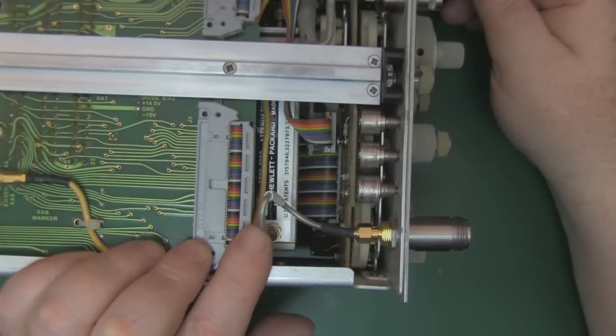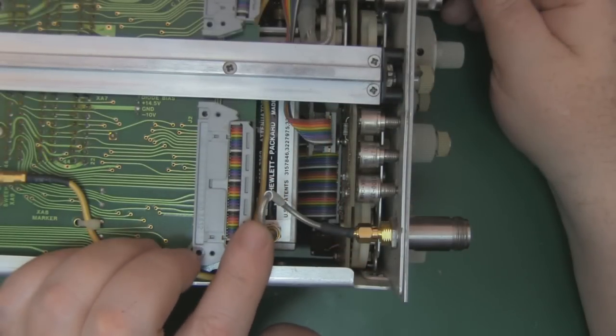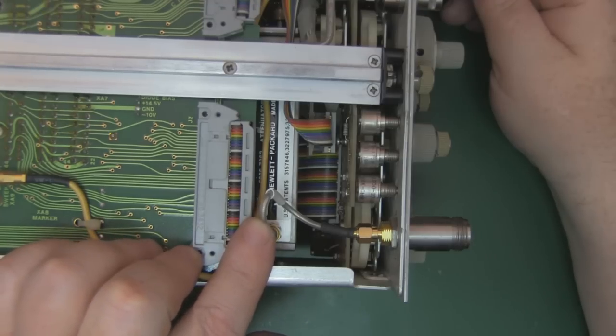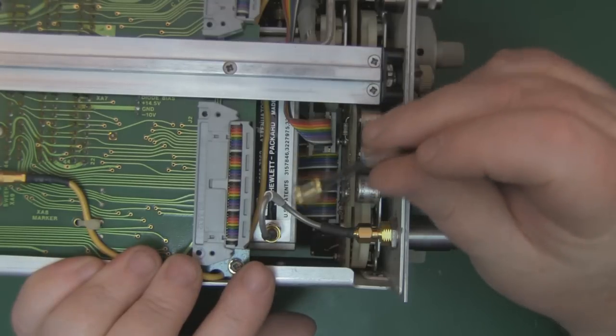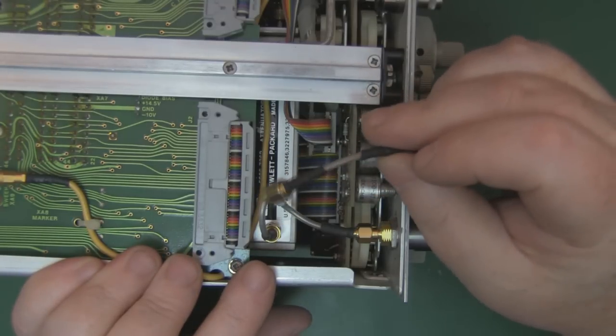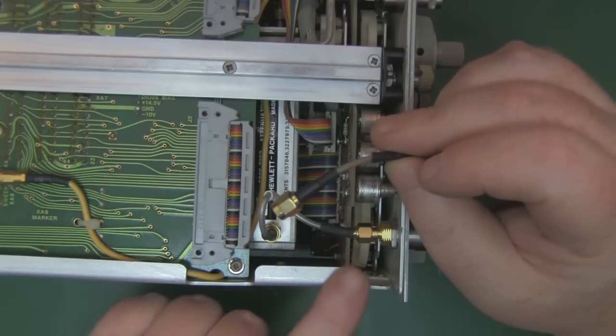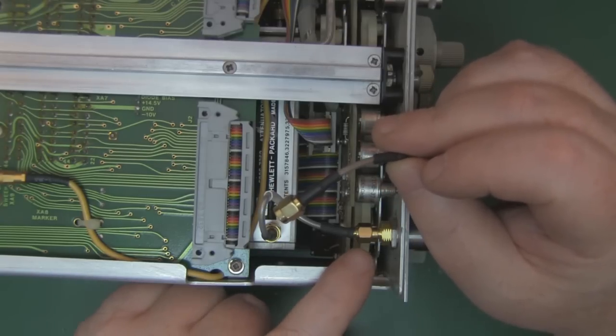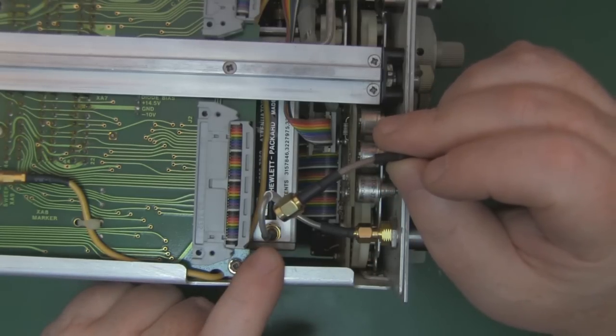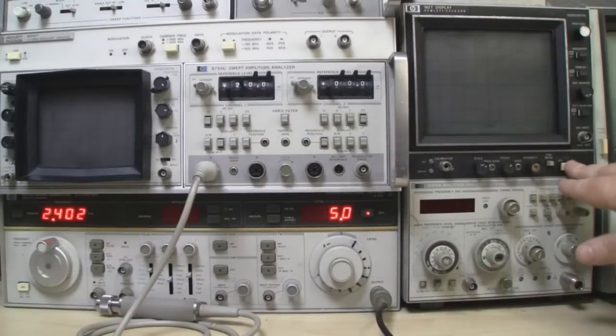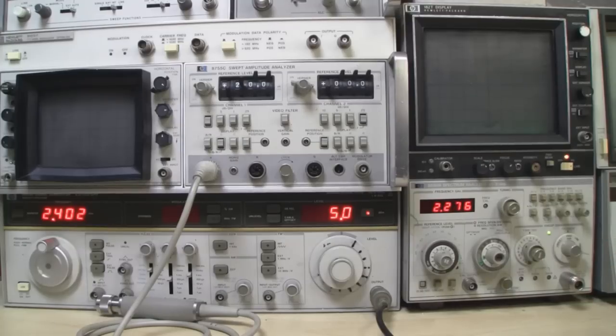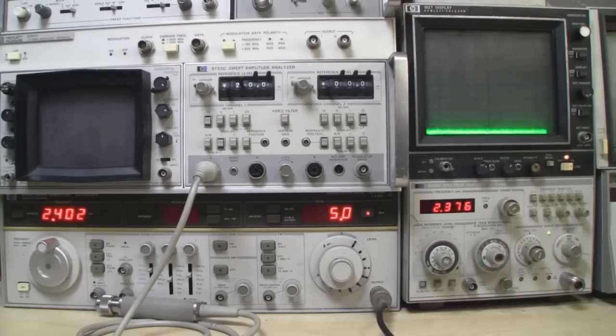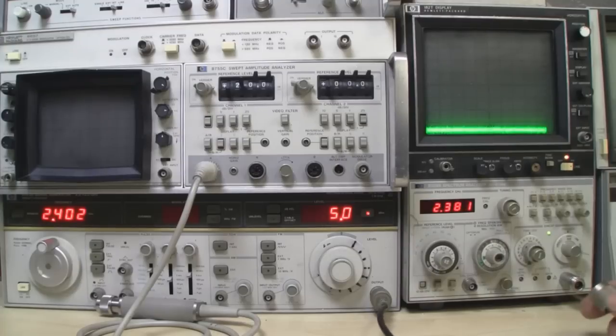So I've got this semi-rigid coax in place but it's a little bit too long. I've got this loop up here and it's going to cause me problems inserting this and removing it again from the mainframe so I've just made up this much shorter length of coax. Because all I'm doing at this stage is just checking whether that cures the problem and we can actually get a signal on the display. So let's switch the spectrum analyzer on then and hopefully now that we've got that quick fix in place we'll see a signal coming out at around the 2.4 mark on the display. And indeed we do.